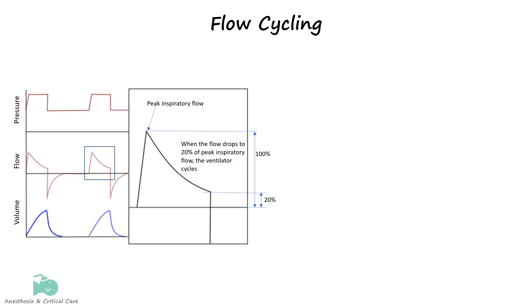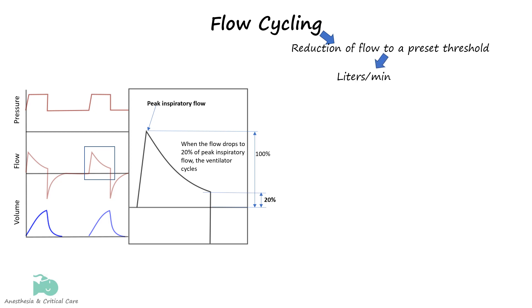With flow-cycled ventilation, the ventilator cycles into the expiratory phase once the flow has decreased to a predetermined value during inspiration. Looking at the flow waveform, we can appreciate that when the flow is reduced to 20% of the peak inspiratory flow, the ventilator cycles into expiration. The flow-cycling variable can be either a fixed flow value measured in liters per minute or a percentage of the peak flow rate achieved during inspiration.